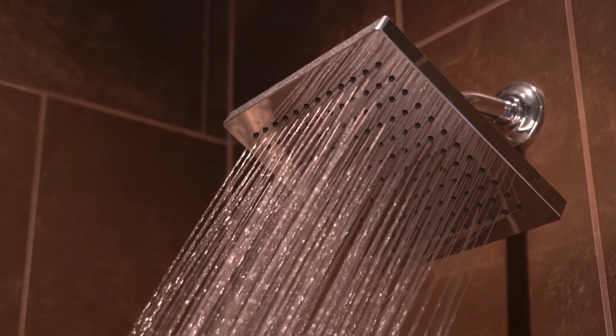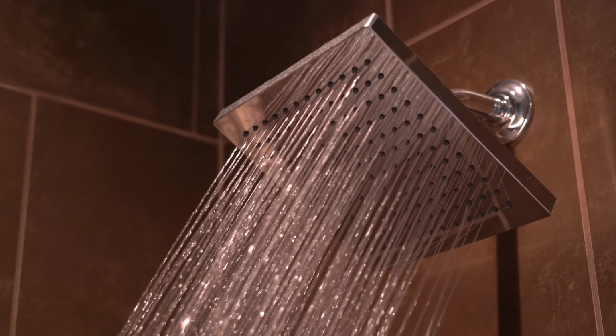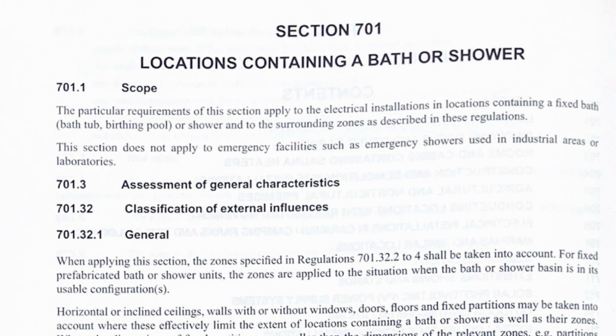One more consideration that I looked at in the regs this week was that the human resistivity of our bodies drops when our skin is wet. This creates a path for current to be able to flow much easier than if it was dry. So, the areas where we are likely to be wet, such as bathrooms, are identified as a particular risk. In bathrooms, we have wet conditions along with wet humans. This is where we get our zones in bathrooms, areas that we need to provide extra protection to avoid human contact with electricity. We might use extra low voltage or IP rated devices. For example, we might use LED lighting in a bath or an electric shower with an IP rating. This is all covered in Regulation 701.